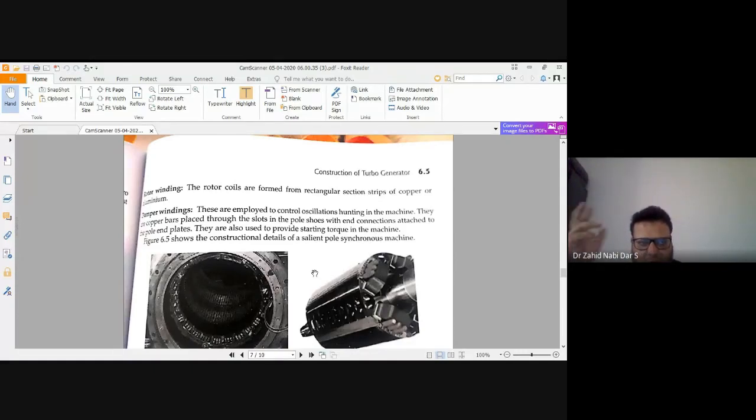So two things can happen. If you are generating less than your demand, load tripping will happen. Load tripping has to happen, otherwise your power system frequency dips down. You have a power frequency range in India, between 49.5 and 50.2 hertz. The lower limit is this, the upper limit is that.